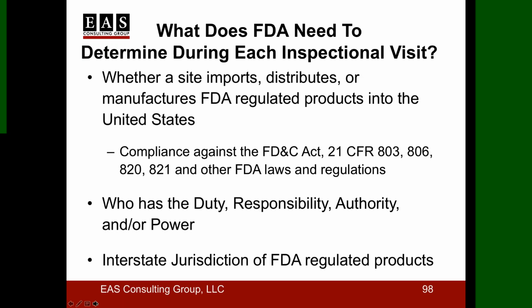They're also, unlike the state, going to have to make sure that something crosses state lines. So for medical devices, it's either a raw material or component from outside of the state. So for example, I'm in Indiana, so outside of the state of Indiana, or you have a customer outside of the state of Indiana. So they have to prove that. If you don't have that interstate jurisdiction by either the component or raw material or customer, therefore it's not a federal action, it's a state action, then FDA will not inspect the company.